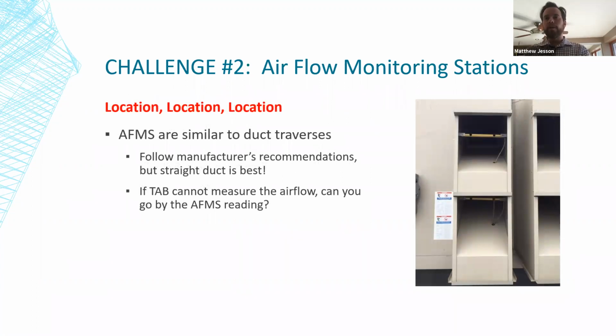If you think of an airflow monitoring station as being similar to a duct traverse, and going back to the straight duct required for a duct traverse and how it works, getting the multiple points of velocity, most airflow stations operate on exactly the same principle. So the manufacturers have their recommendations for where to locate them, and go by those, but bear in mind that if you've got good straight ductwork, that's your best case scenario. And if a test and balance technician can't measure that airflow, then can you trust what the airflow station is reading? Again, nothing against airflow stations, but there are many things that can affect their reading that might lead you to get an incorrect airflow measurement.